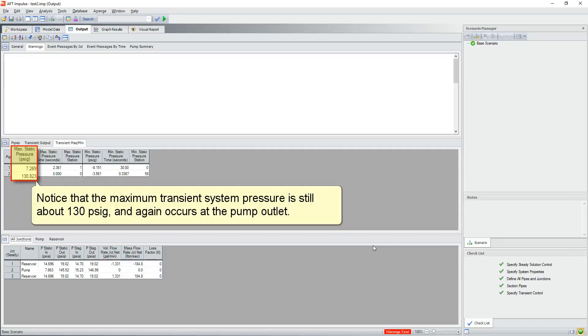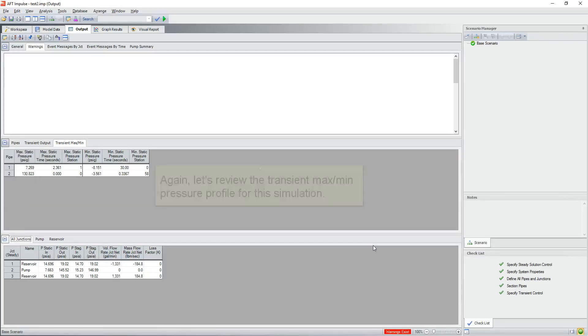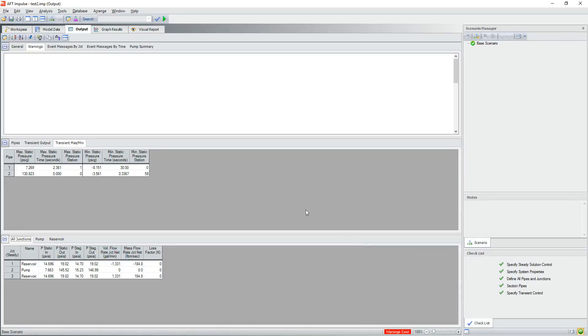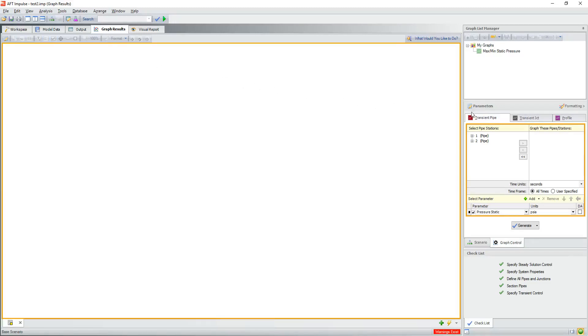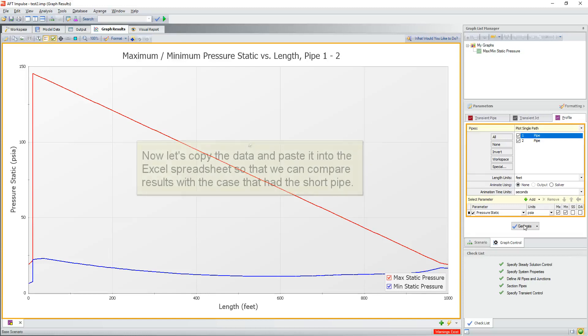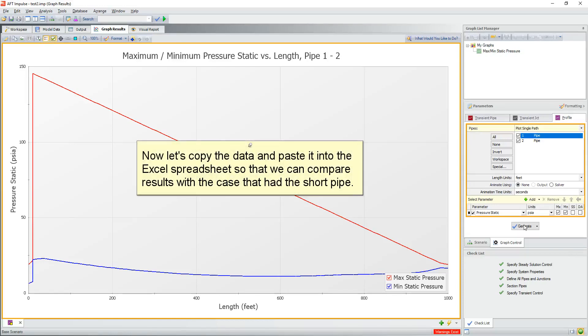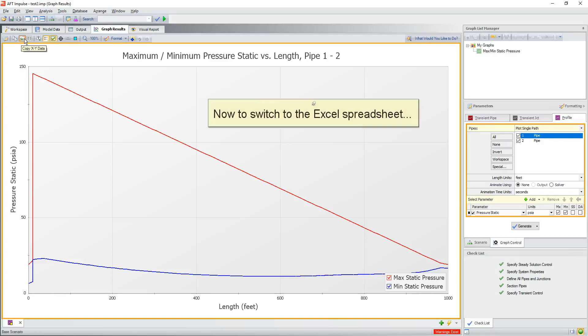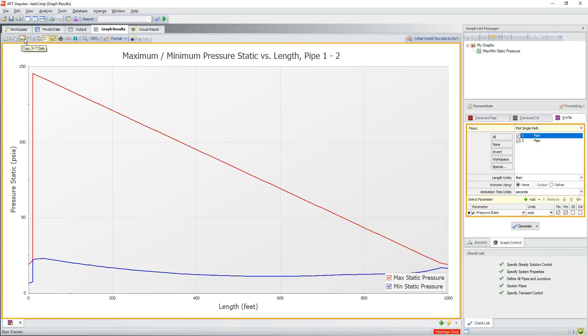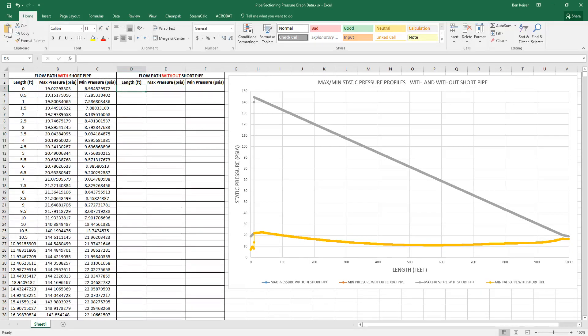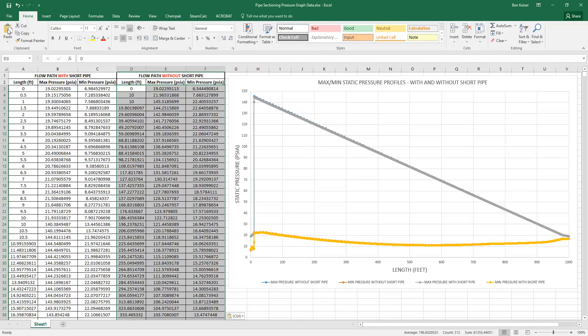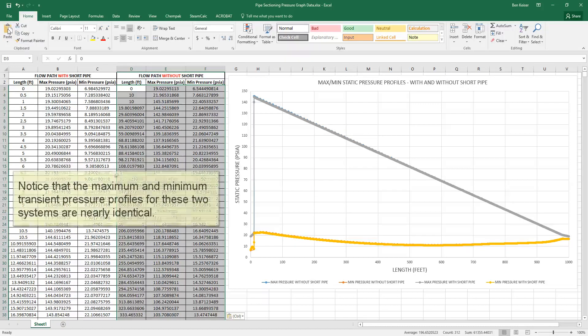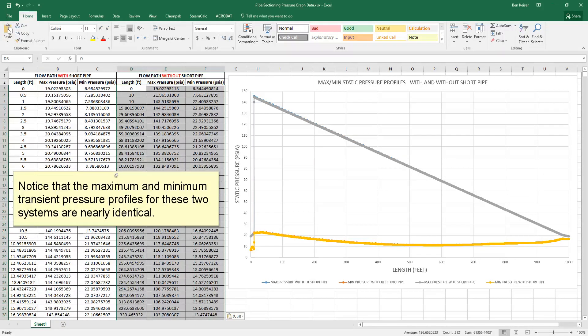Notice that the maximum transient system pressure is still about 130 PSIG and again occurs at the pump outlet. Again, let's review the transient maximum pressure profile for this simulation. Now let's copy the data and paste it into the Excel spreadsheet so that we can compare results of the case that had the short pipe. Now switching back to the Excel spreadsheet. The data has now been pasted into the spreadsheet and the graph was pre-programmed to automatically plot the data once pasted. Notice that the maximum and minimum transient pressure profiles for these two systems are nearly identical.